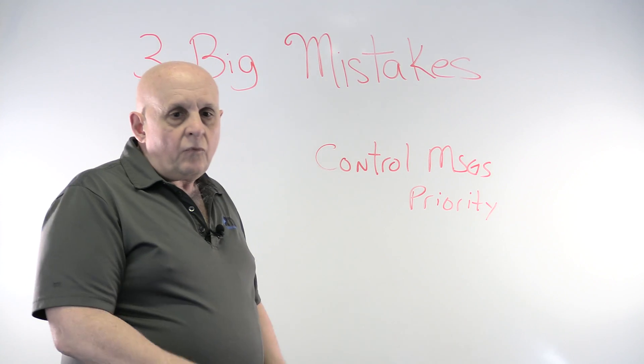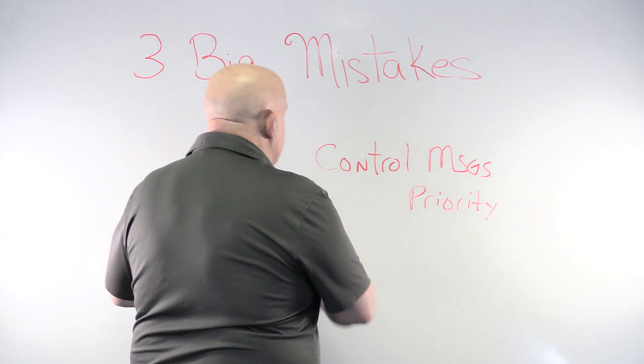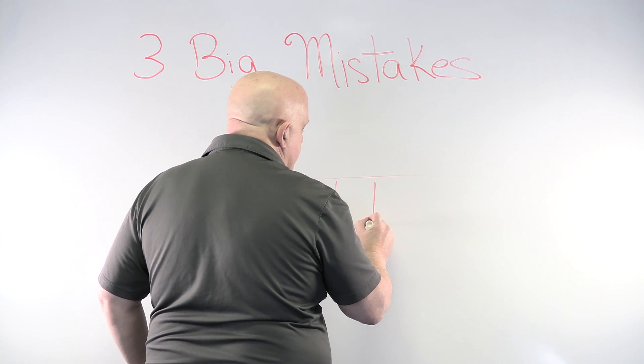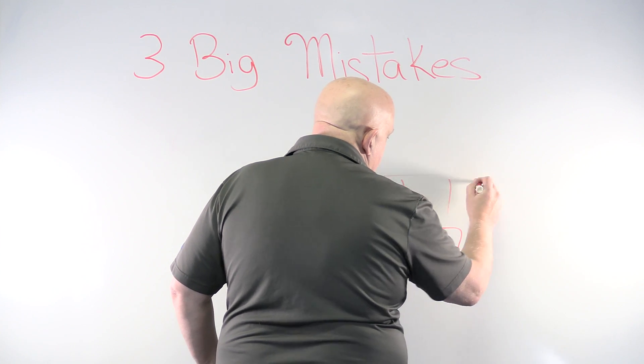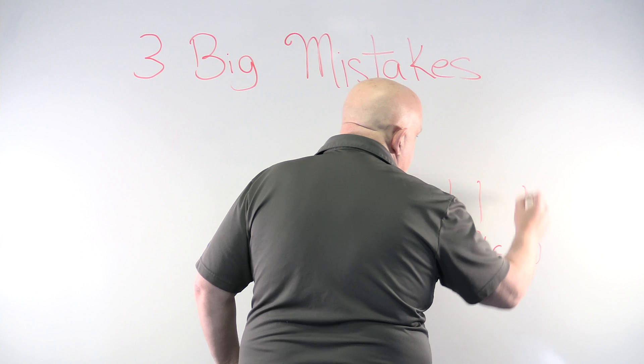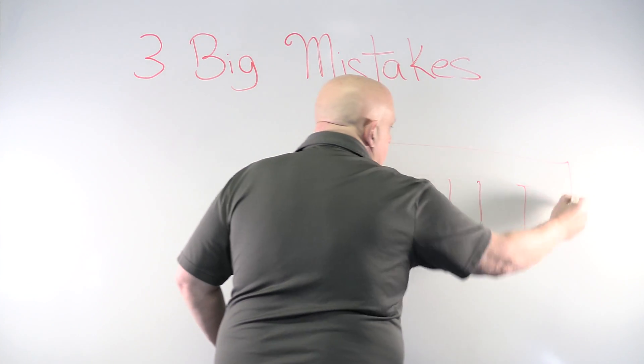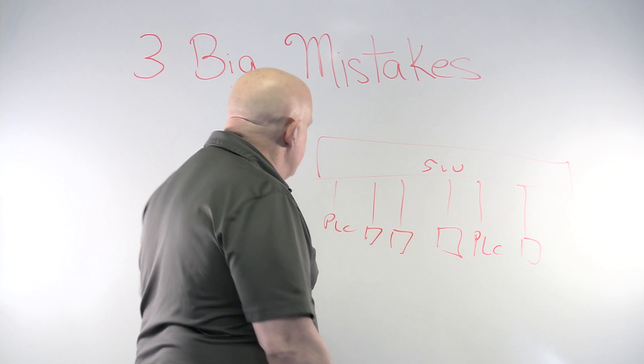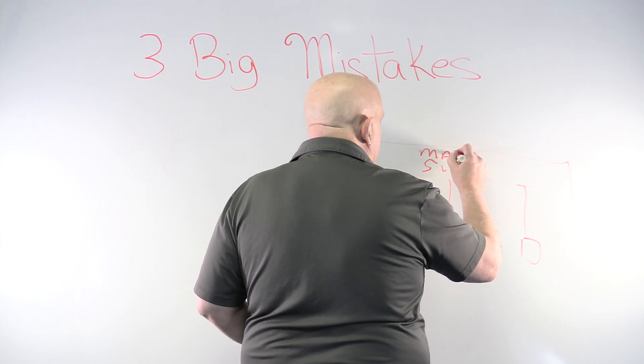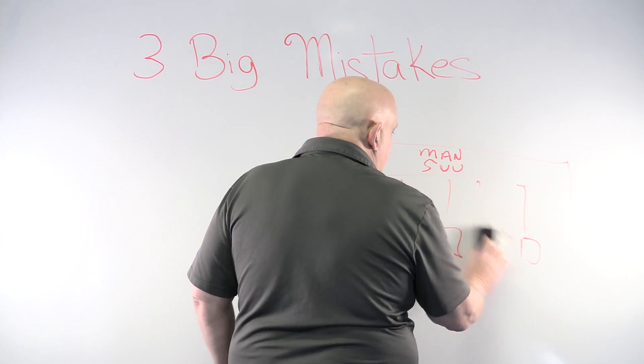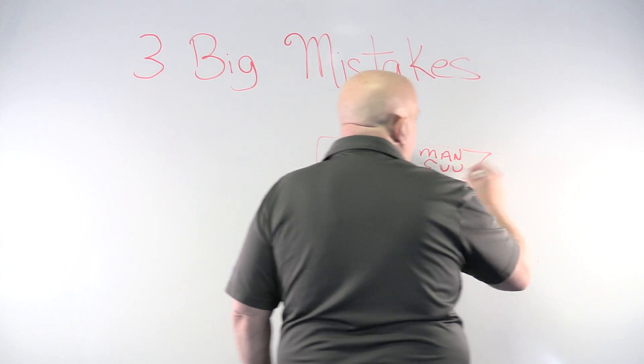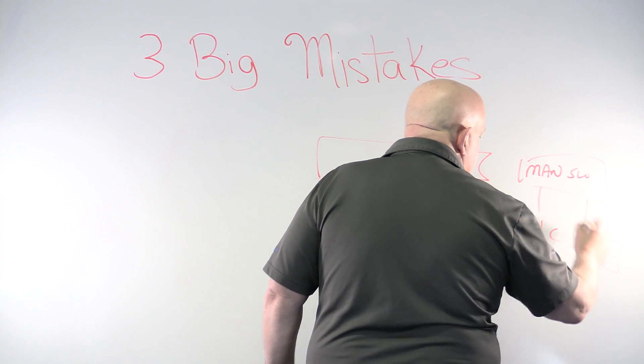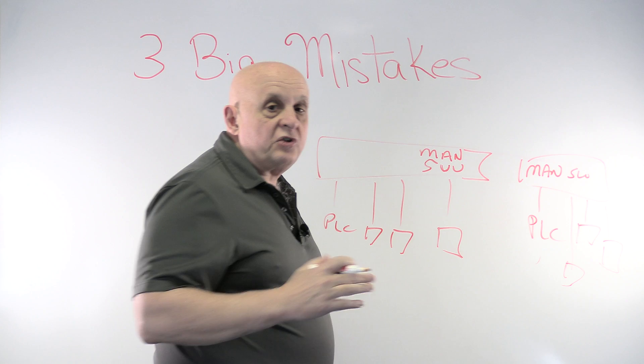The third mistake is that people put together a network, drop a PLC here, add some devices, add another PLC, more devices — all off a switch — without thinking about how to architect it properly. The optimal way is: for every PLC you have one managed switch. If you have a second PLC, you buy a second managed switch for it. You segment these networks so each control network has one PLC that essentially provides one function.